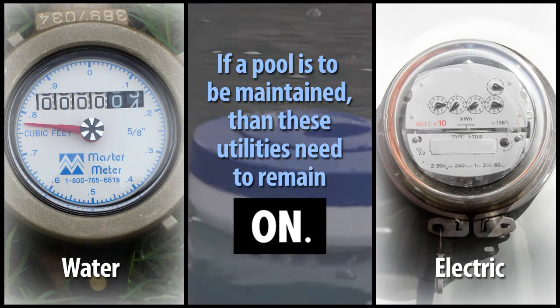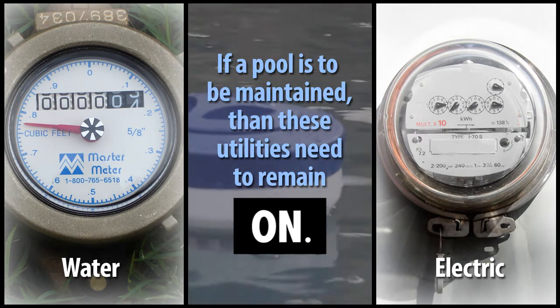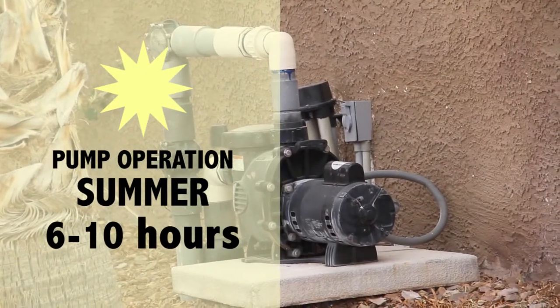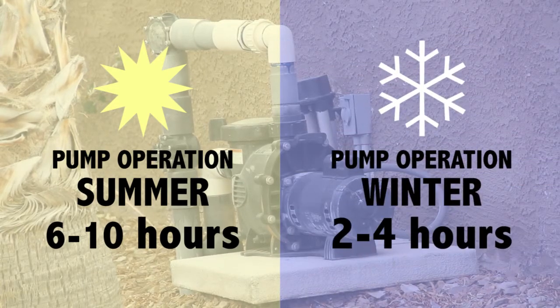to keep daily circulation. Pump operation requirements in the summer months is a minimum of 6 to 10 hours, and in the winter months, 2 to 4 hours minimum.